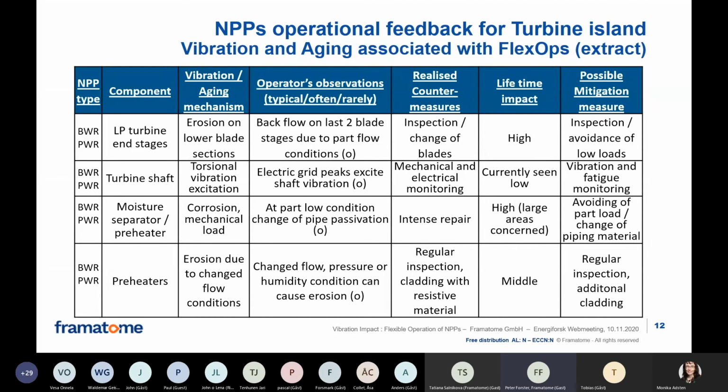Mechanical and electrical monitoring have been made. On the other hand, the lifetime impact is not so high, or seen as low at the moment, but the vibration and fatigue monitoring is still continued. So the third row is dealing with the moisture separator reheater.